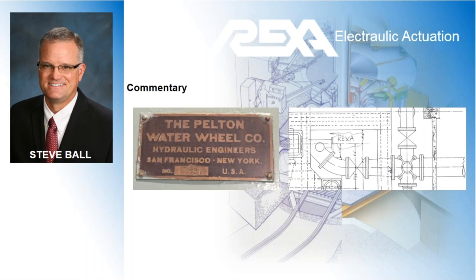We tested this system out when it was ready for commissioning with load banks. I think we set about 5.5 megawatts worth of resistive load out on the side of the plant, and we were able to incrementally add and subtract load, I think in increments as small as 50 kW. It was originally supposed to be a graded test where we would start off with, say, half a megawatt to 750 kilowatts, then add about half a megawatt to it and allow the governor to still do its job, but it would obviously not have enough water. So that meant a control system that recognized that and sent a signal to the Rexa to begin opening the needle valve until the frequency was recovered and satisfied.